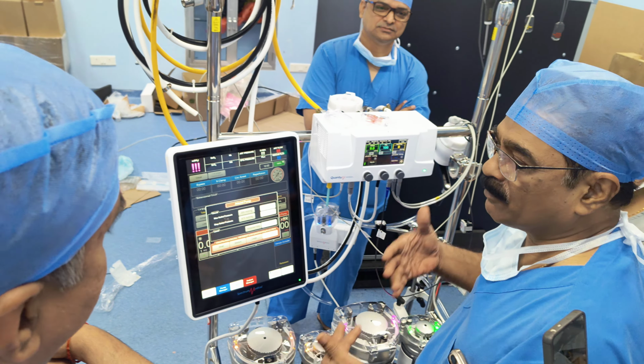So you have flow. Now this flow, what you are seeing here is the calculated flow. What you see coming through this will be a little different. It's a measured flow, because it will be minus all the shunt lines: your sampling line, your recirculation line, your hemofiltration line. But what is going to the patient will only be sensed by this and it will be displayed.